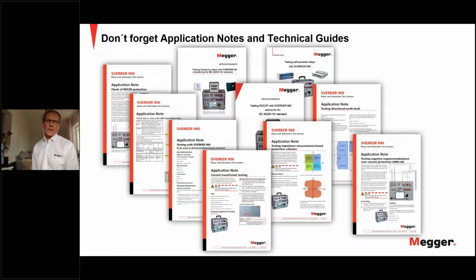I would also like to highlight we have a lot of application notes for when you're doing tests with Sverker 900. For example, when you're doing current transformer testing, all tests you would like to do with the current transformer, it's described here how you do with Sverker 900. Also, testing impedance measurement based protection schemes. This is when you're testing distance protections. This is made mainly in manual mode. Testing direction of fault, we have testing negative sequence, unbalance over current protections, and so on. This is possible to find on the Megger web page.